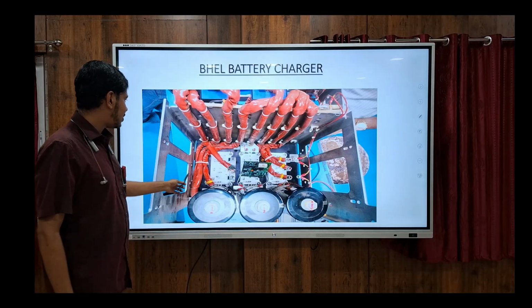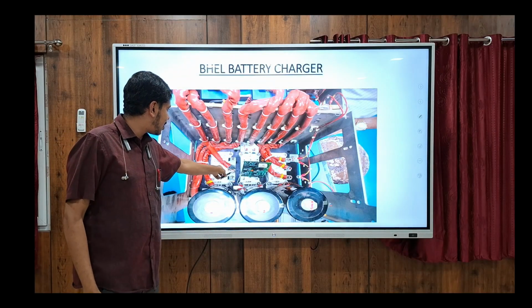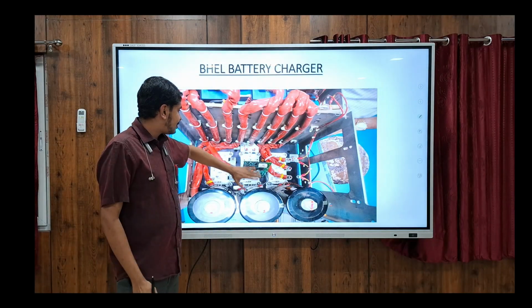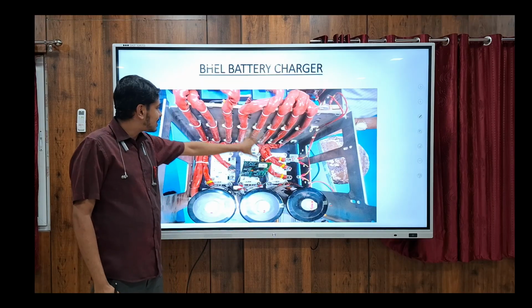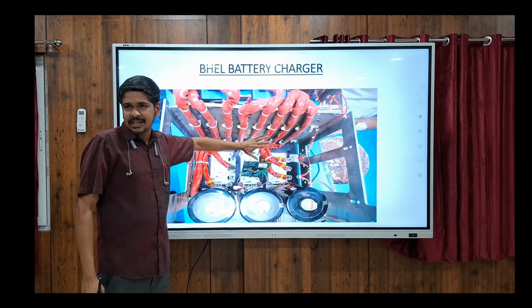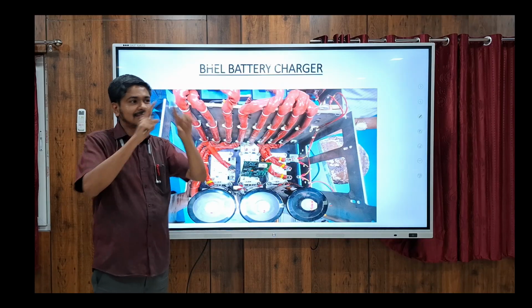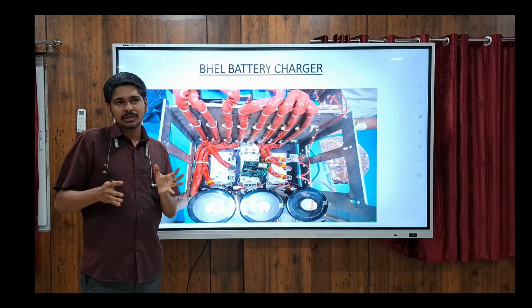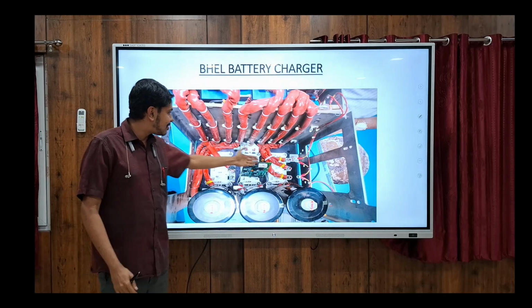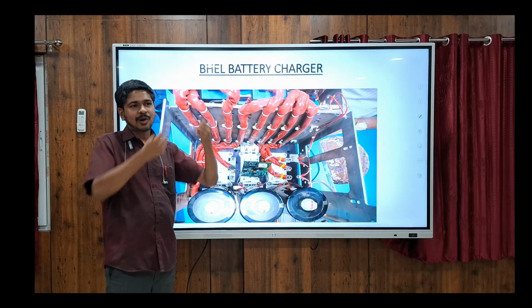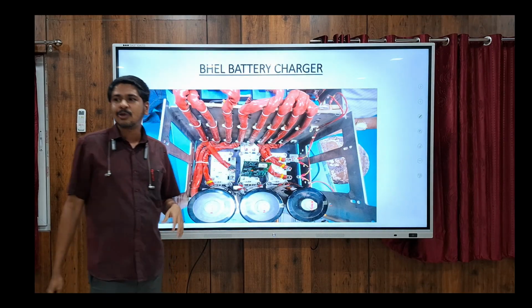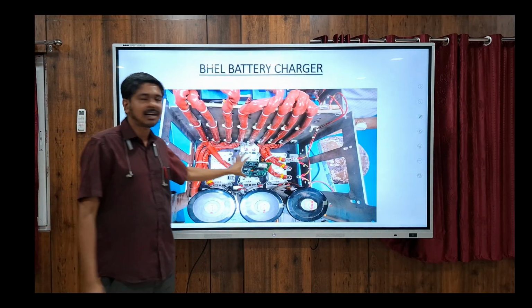So that was the condition, and here the flash mark was there. Above it, DC link capacitors, other sensors, all other things are mounted above this module, and this is also a box type enclosure, so at the bottom portion we cannot see what is happening. We have to unload and dismantle the full module, then only we will be able to see what is going on inside.